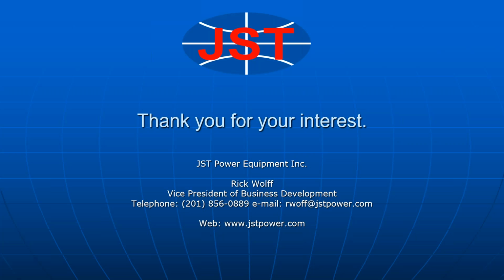Okay, a question came in. Is there any difference in the temperature ratings of a cast resin transformer when compared to a VPI transformer? Yes. Basically, all transformers are specified with a temperature rise, and this is a question I get a lot. They say, oh, okay, the varnish type transformer, VPI, that's a 220-degree insulation system, so that's better than cast. You only have 180. That's not really the way to look at it.